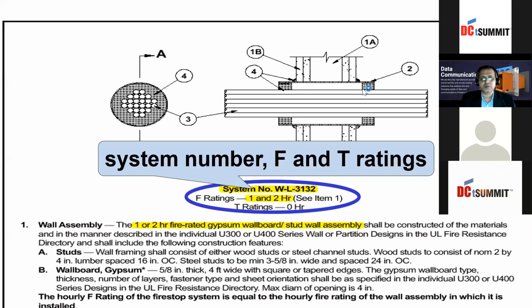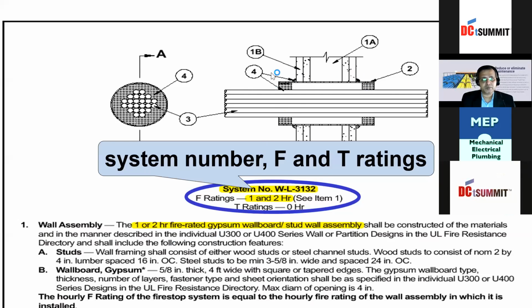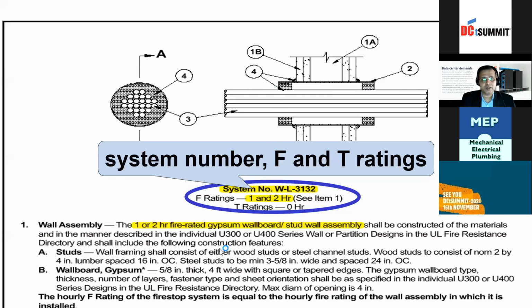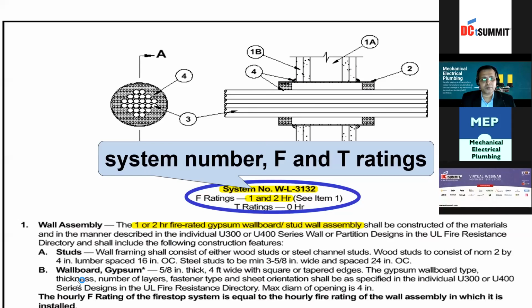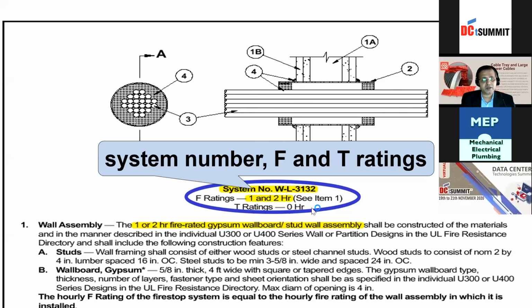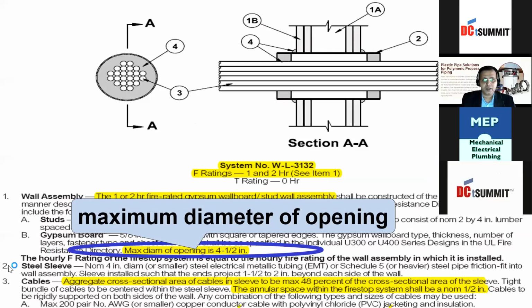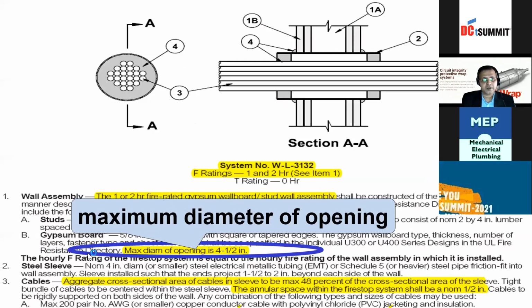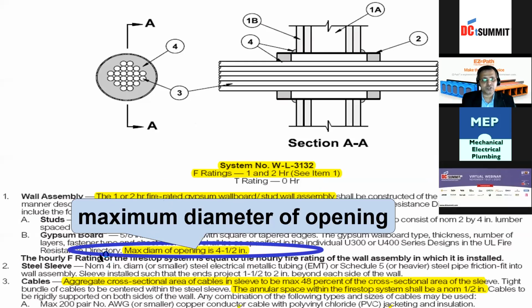What is passing through this is a cable tray which is passing through the fire rated gypsum wall. Now you can see the cables. What are the diameters of the cables is also mentioned in this UL tested system. And what is the maximum diameter size of the opening is also mentioned in this system. Now, description of penetration, as I mentioned, what is the penetrant which is passing through this is also mentioned in this UL tested system. The most important part is the last one.